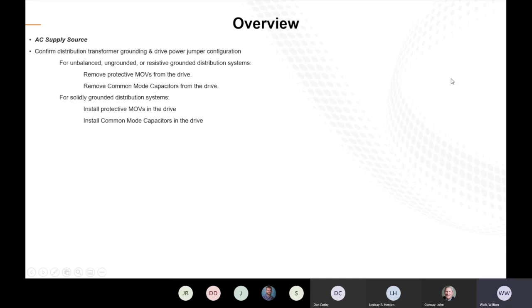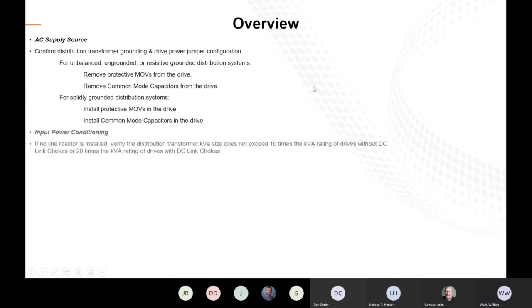So a real quick overview here. For your AC power supply, ensure that you have the proper configuration when it comes to your power jumpers, whether you have a solid grounded or a high resistance ground. You might want to consider removing those jumpers. For your input powering condition here, like I said before, if you don't have any line reactors, just make sure that your transformer in the facility doesn't exceed 10 times the kVA of what the drive is rated for, which you can find close to the catalog number of the VFD, or 20 times that if you have a DC link choke.